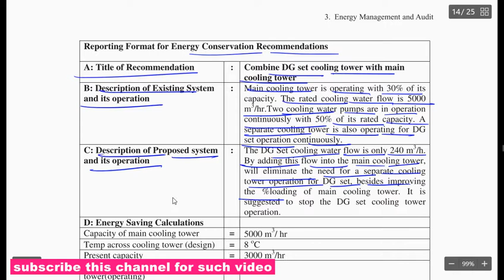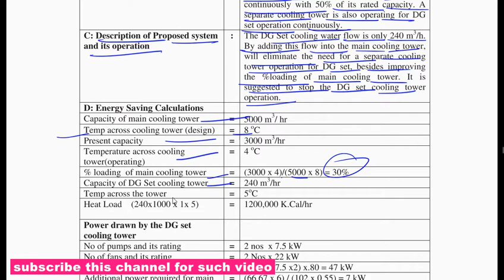Energy saving calculation: capacity of main cooling tower is 5000 meter cube per hour. Temperature across cooling tower is 8 degrees Celsius. Present capacity is 3000 meter cube per hour. Temperature across cooling tower is 4 degrees Celsius. Loading of main cooling tower is 3000 into 4 by 5000 into 8, that is 30%. Capacity of DG Set cooling tower is 240 meter cube per hour. Temperature across the tower is 5 degrees Celsius.